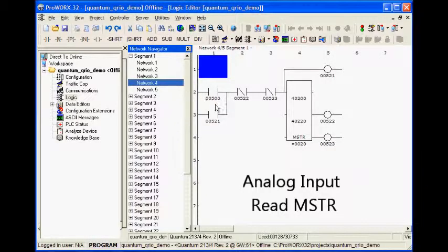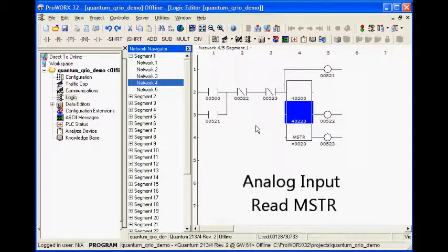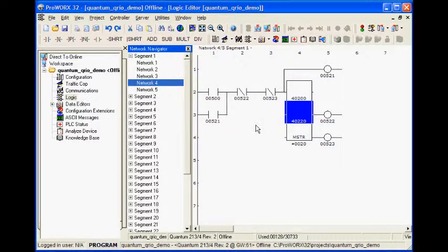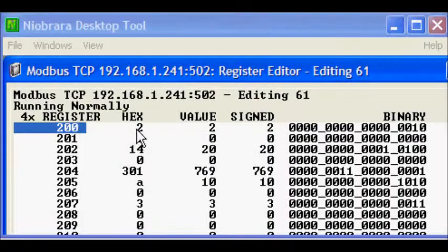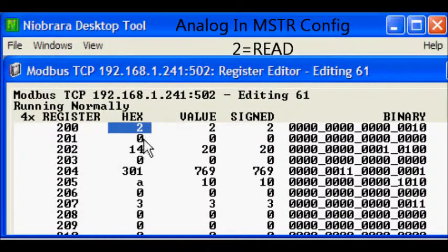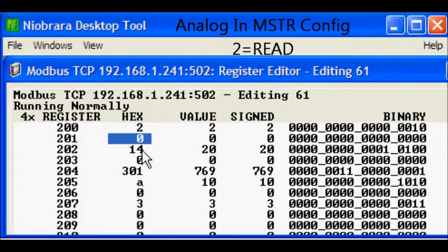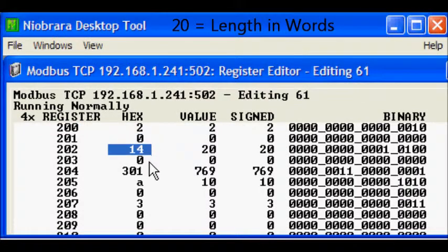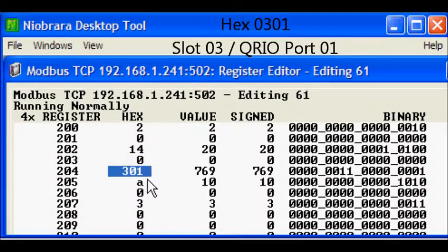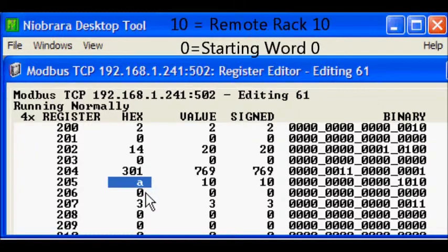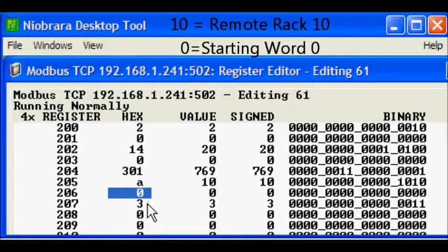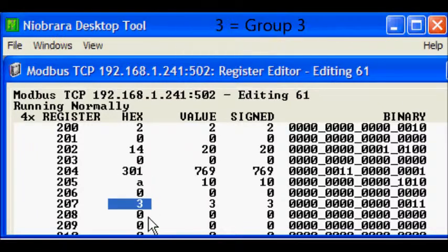Network 4 has the MSTR used to read the analog input card. The control block for the MSTR starts at register 200. The value 2 selects a read operation. The word length is 20. Also defined are the QRIO slot and port and the rack, group, and slot of the analog input card.